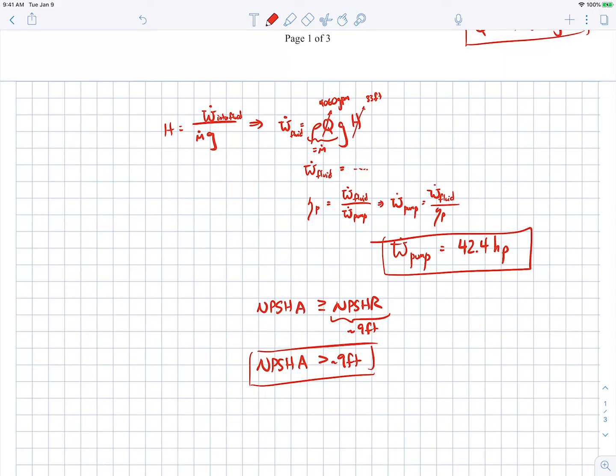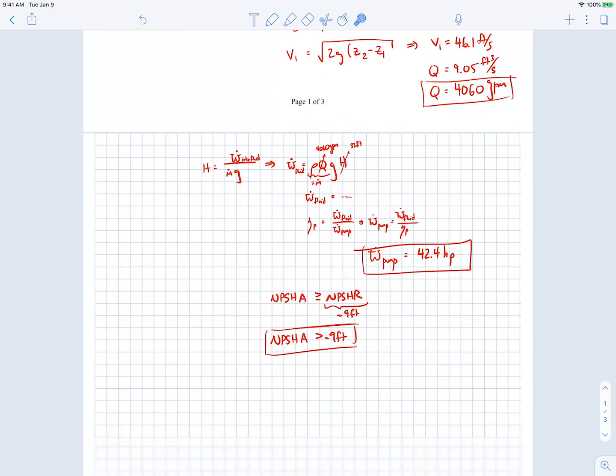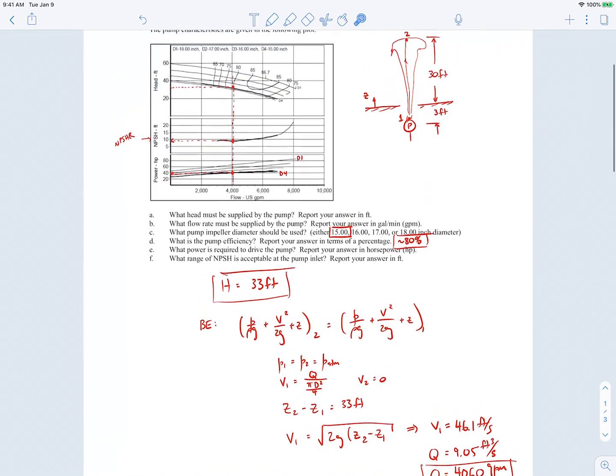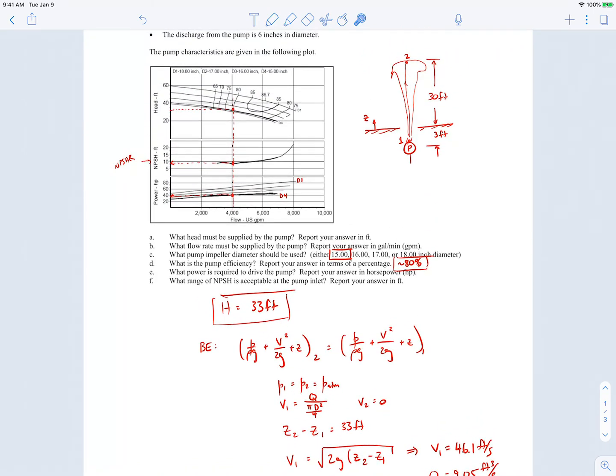So the NPSH A that we have to supply to that pump should be ideally greater than about nine feet. We just need to make sure that our pipe system is set up such that we have more than nine feet of head, or at least nine feet of NPSH A leading into the pump so we can avoid any cavitation. So that's it for this example. It's pretty straightforward for the most part.